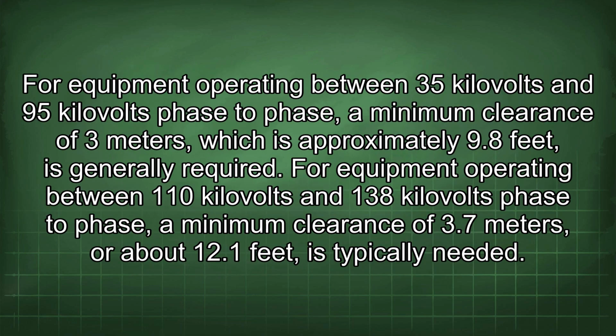For equipment operating between 35 kilovolts and 95 kilovolts phase-to-phase, a minimum clearance of 3 meters, which is approximately 9.8 feet, is generally required. For equipment operating between 110 kilovolts and 138 kilovolts phase-to-phase, a minimum clearance of 3.7 meters, or about 12.1 feet, is typically needed.